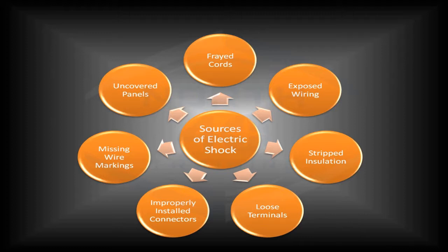Missing wire markings are all too common. We've all run into those on the job site where you go out and think one of those three wires was the neutral or ground wire. You hook it up, turns out it wasn't. You create a huge flash, or you've tripped some expensive ground fault path device, or blown some fuses. That all comes back to missing wire markings, which could have been prevented at the onset of the installation.